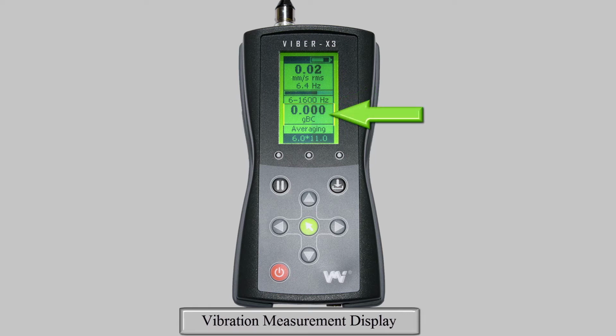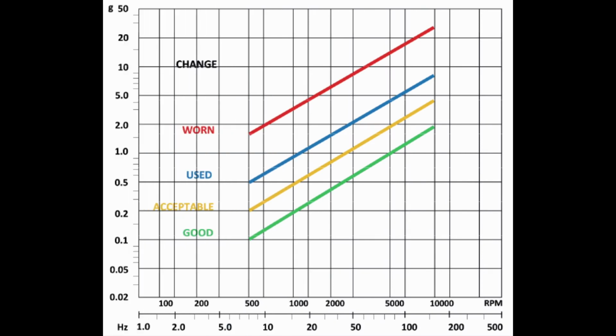The Viber X3 also gives a bearing condition measurement. This is shown here. This takes a reading from the frequency range of 500 Hz to 16 kHz and measures the average change in velocity of the vibrations as the unit G. This cuts out noise and vibrations from machine imbalance and misalignment. A high value can indicate poorly lubricated or damaged bearings, and further investigation is recommended. VMI recommends consulting this graph, which is also provided in your instruction manual.